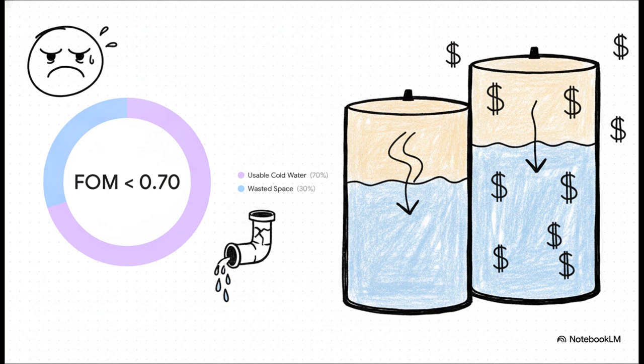Now compare that to an unstratified tank with a low figure of merit, anything below 0.7. Because of premature mixing inside the tank, over 30% of the tank's volume is completely wasted. It's just dead space holding useless, lukewarm water. To get the exact same amount of emergency ride-through time as the highly stratified tank, data centers with poor stratification are forced to build massively larger, incredibly expensive tanks, eating up valuable facility space and capital.